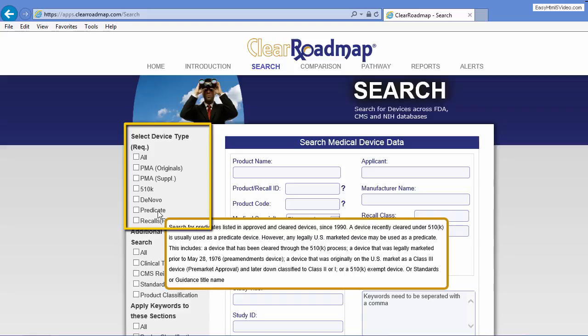In many ways, you can find what's called the grandfather device, the device that has been used by industry over and over and over again as the predicate. These predicates are what a 510K application uses to establish substantial equivalence. Again, it can be a K number, a BK number, or a recognized standard.